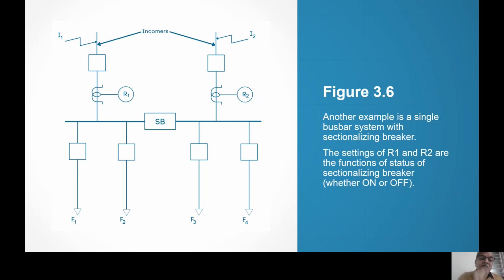Not only that, but when the sectionalizing breaker is on, both the incomers are in parallel. Therefore, if one incomer has impedance Z, then the total impedance will be Z by 2. Therefore, fault current will be large. But if the sectionalizing breaker is off, fault current will be less. And therefore, TMS also will be different, right? You see, you need two different sets for relays R1 and R2 in such a case when you have this sectionalizing breaker. So I have given you these two examples. As I told you, I can give you 100 examples in the prevalent power system, but the time will not permit.